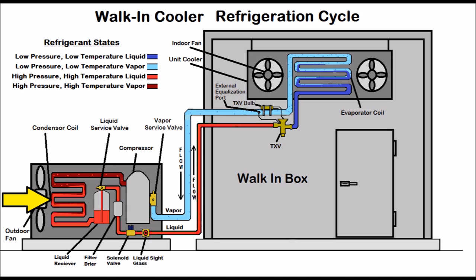That's the saturated state, and that's where most of the heat is being rejected. There is no temperature change once it hits that saturated state. Then it continues to reject heat until it turns into a complete liquid. The liquid refrigerant then lowers in temperature as it rejects heat and turns into a sub-cooled liquid.